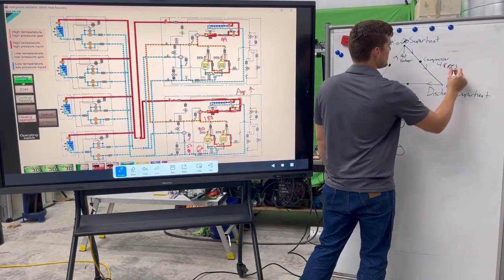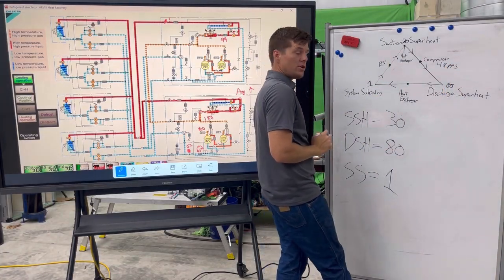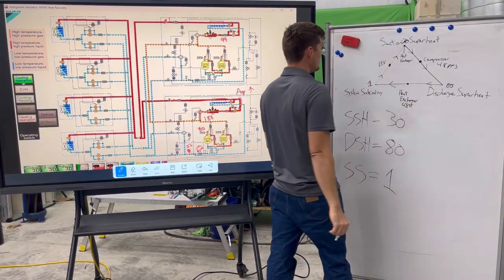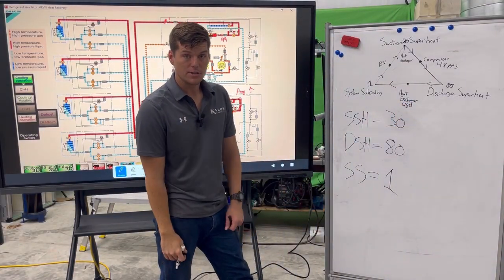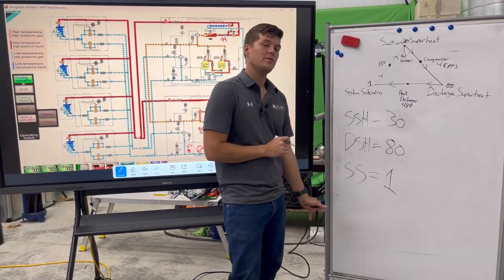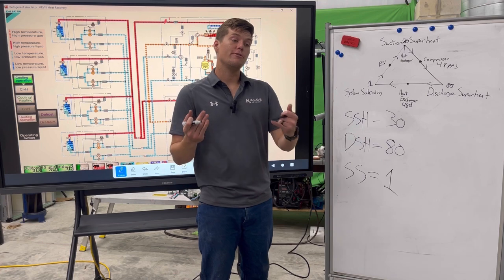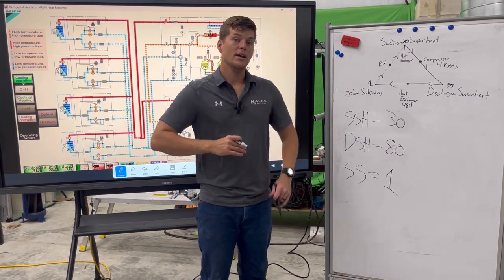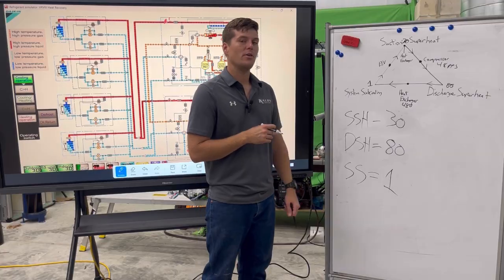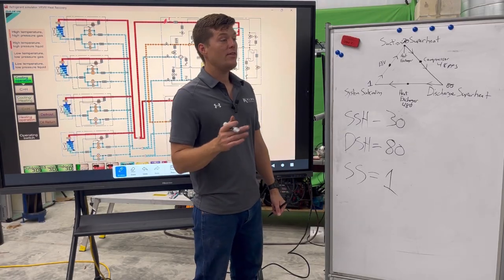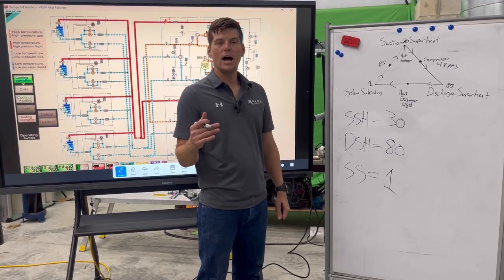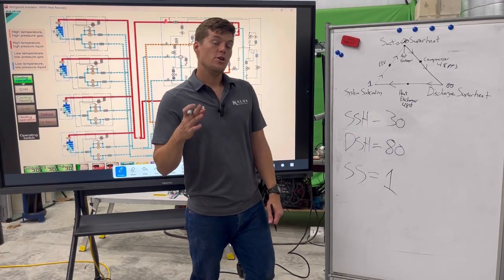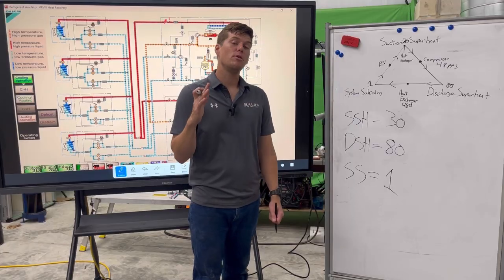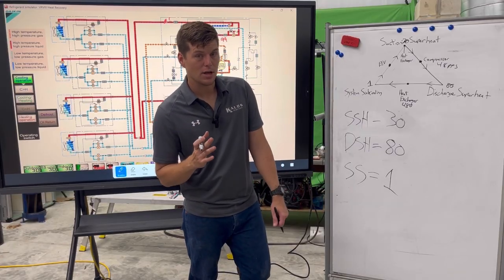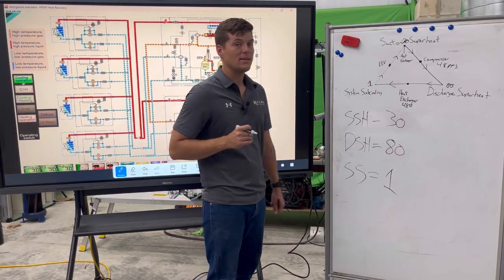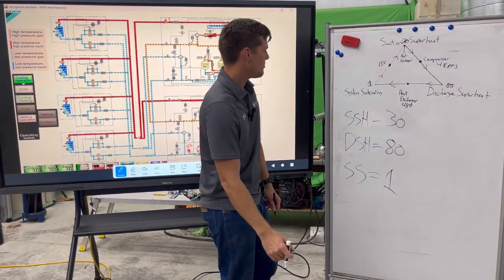Okay, let's keep moving our way around the triangle. What about my outdoor heat exchanger? My outdoor heat exchanger is at 480 pulses. It's wide open. Okay, so it's not metering refrigerant. It's not metering subcooling. You'll find on larger, newer VRF systems the ability to actually meter the flow of liquid refrigerant from the outdoor heat exchanger in cooling to modulate the subcooling number, based upon the load. So it's going to try to maintain a specific number, and that pulses amount, whether it's low or high, is going to tell me where it falls in that charge range. You'll find with newer equipment they usually run around half pulses to maintain that 9 to 11 degree subcooling amount on the outdoor heat exchanger. On older models like this, it's going to be wide open because it doesn't have the programming for that.